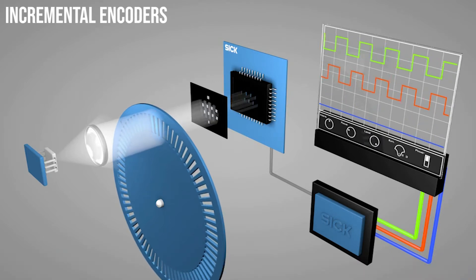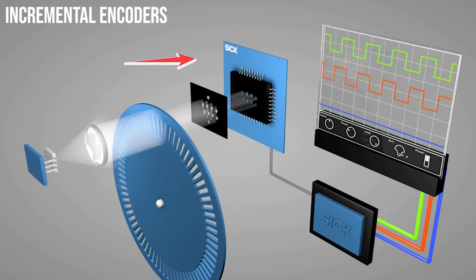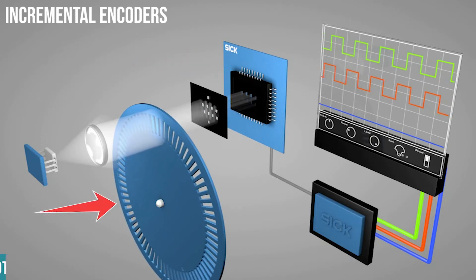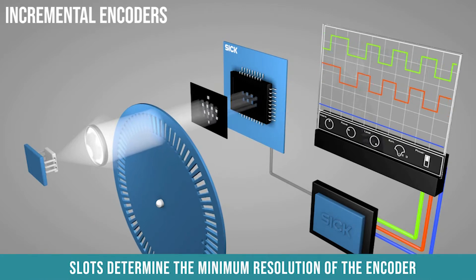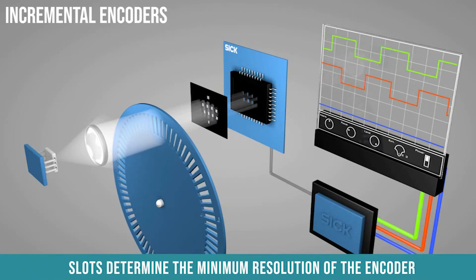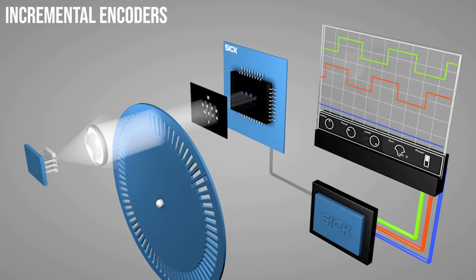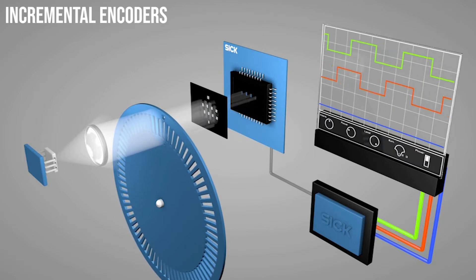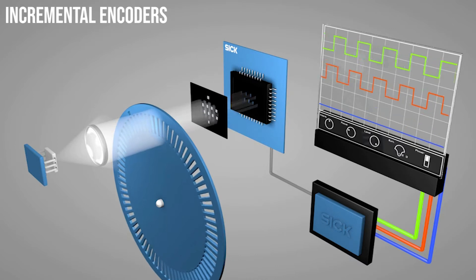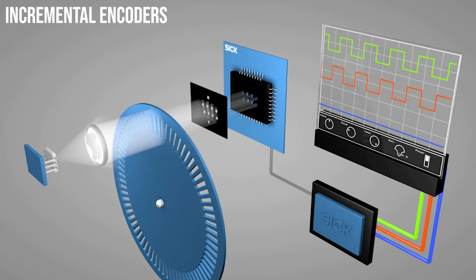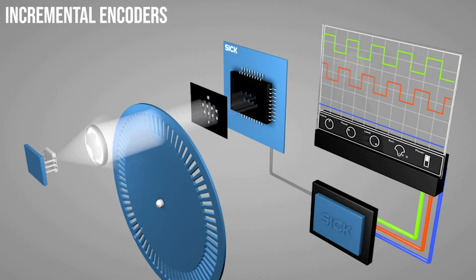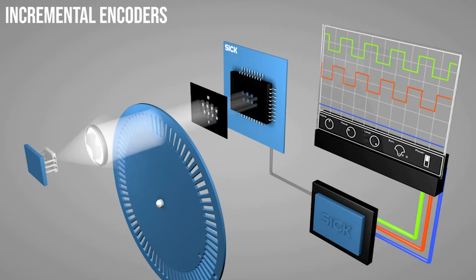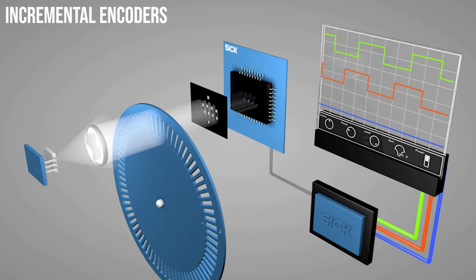Here's how they work. Inside the encoder is a light emitter and receiver, as well as a rotating disc with many little slots cut into it. These slots determine the minimum resolution of the encoder. As light passes through and is blocked by the slots in the disc, the encoder knows how far the disc is turned. Every time the light receiver receives a new pulse of light through the disc, it knows the encoder has moved a very small amount. The encoder gives pulsed output based on every increment of movement or resolution.